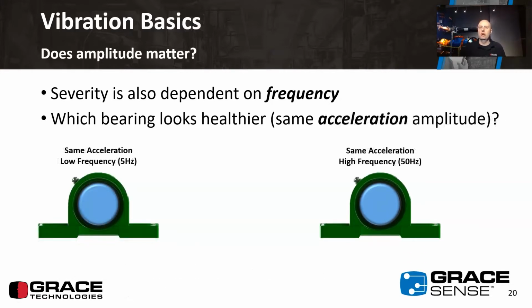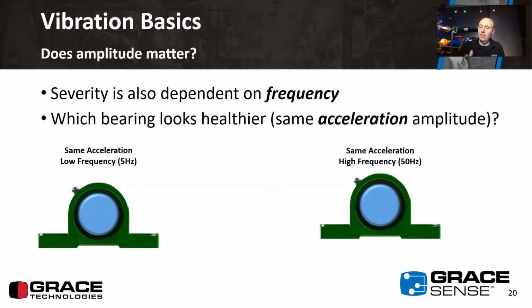Now if we look at acceleration, these two bearings are experiencing the same acceleration at different frequencies. The one on the left is low frequency, the one on the right is high frequency. So I'll turn these on. The one on the left here, at low frequency, looks a lot worse off than the one on the right. The take home here is that if you're looking at acceleration, that's more damaging at low frequency. So it's kind of the opposite to what we just saw in the displacement sense.